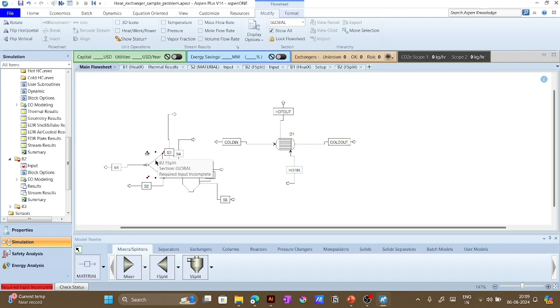Let's say there is some disturbance in the input stream S1: instead of 1000 kg flow rate, now it's become 800. But you still want that regardless of what changed in S1, let's say I want to maintain 700 here. So what this will do is prioritize S3 first and then look for S4. So if I'm saying S3 should be 700, I'm limiting the flow of S3 to 700. So if the flow falls to 700, it will go to S3 only and S4 will be 0. So you have better control.